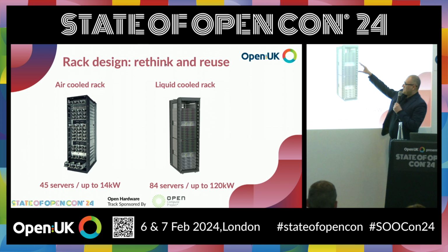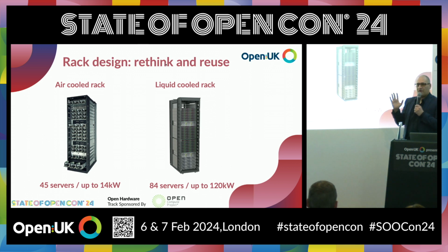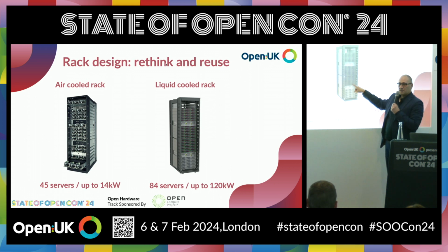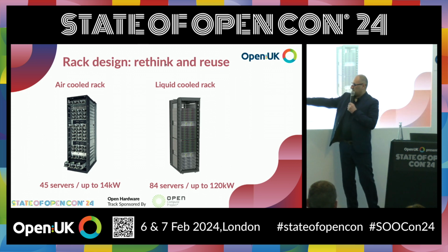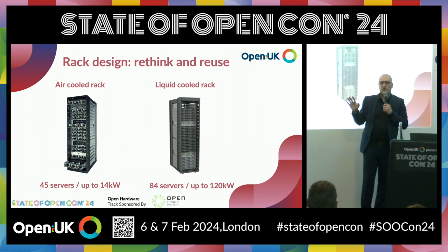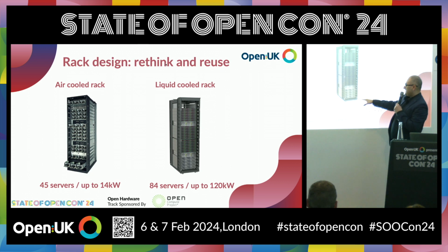Overall we have 72 plus 12, 84 servers, which is still pretty good for cloud operation or high-performance computing. But each server's energy consumption is the same as here. It's roughly 300 watts, 400 watts, but the density now, with the same servers, is 27 kilowatts. And this is how we achieve 3 times more density, more performance, less energy consumption, and higher temperatures, which allow us to make heat reuse. So many things have happened. Thank you.